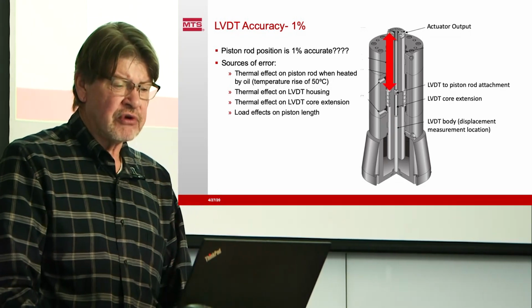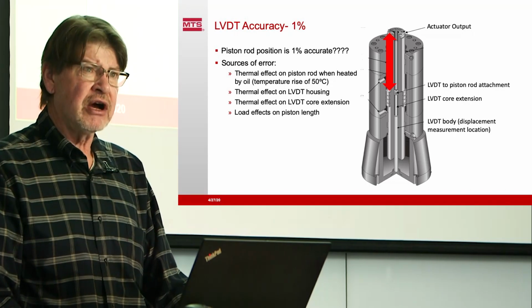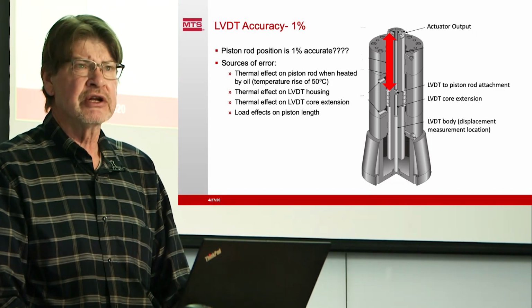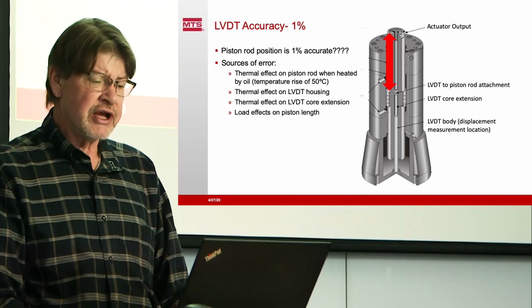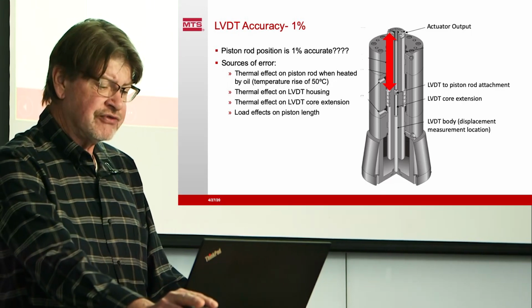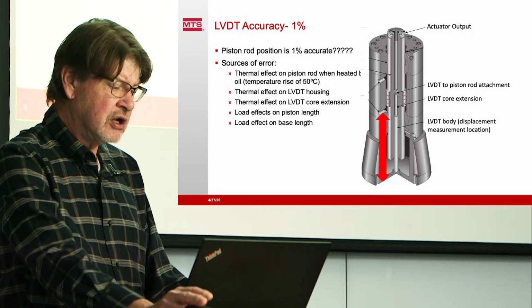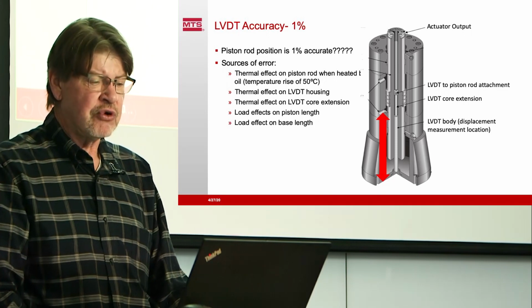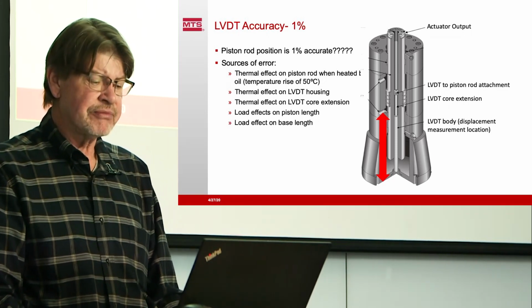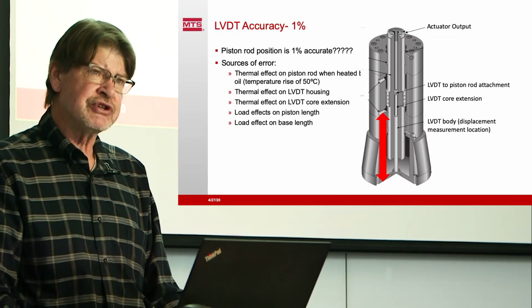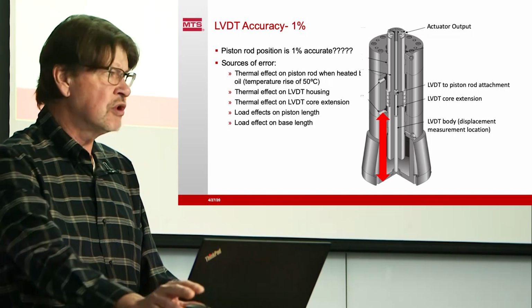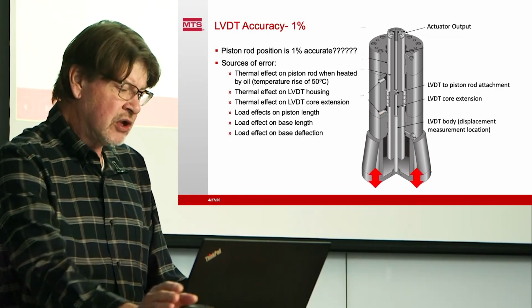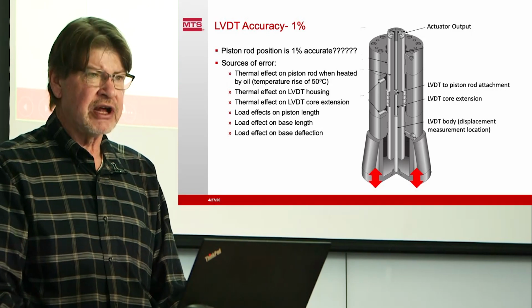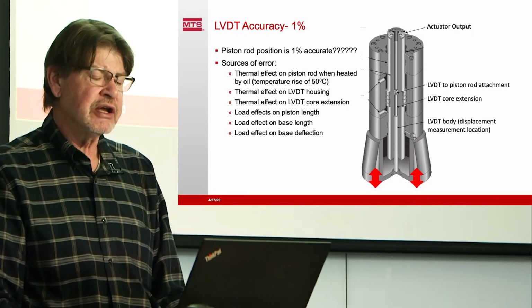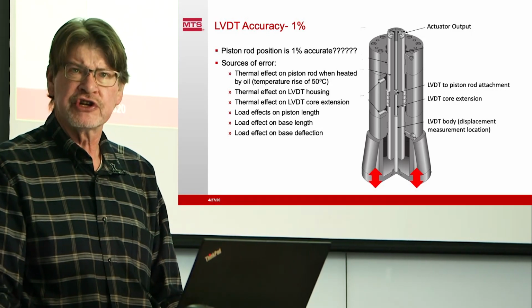Load effect on piston rod length. If we push on that piston rod or pull on the piston rod, it's going to get longer or shorter. So that's going to change the position relative to where the LVDT is measuring it. Load effect on the base. If we push with the actuator, we're going to compress the base. So that means that the piston rod is going to move down relative to where we think it is. Load effect on base deflection. This is mounted to a base plate or a bracket of some kind. That's likely to move as well under changing load.